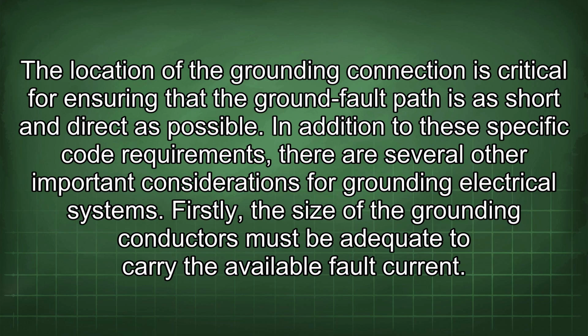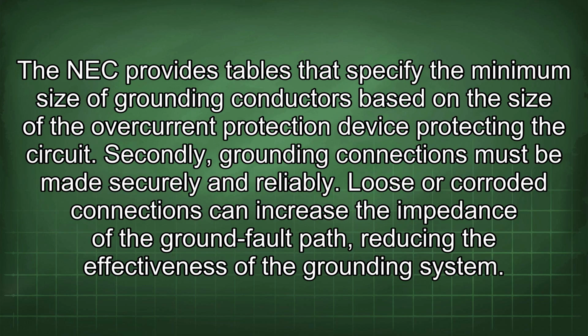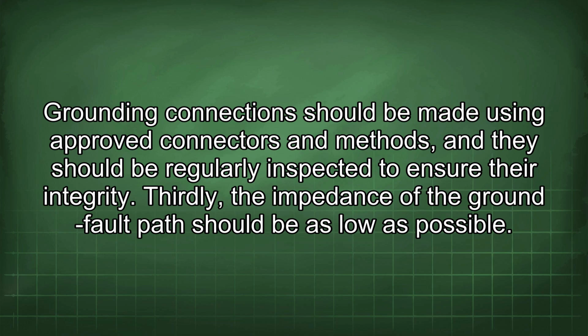as possible. In addition to these specific code requirements, there are several other important considerations for grounding electrical systems. Firstly, the size of the grounding conductors must be adequate to carry the available fault current. The NEC provides tables that specify the minimum size of grounding conductors based on the size of the overcurrent protection device protecting the circuit. Secondly, grounding connections must be made securely and reliably. Loose or corroded connections can increase the impedance of the ground fault path, reducing the effectiveness of the grounding system. Grounding connections should be made using approved connectors and methods, and they should be regularly inspected to ensure their integrity.